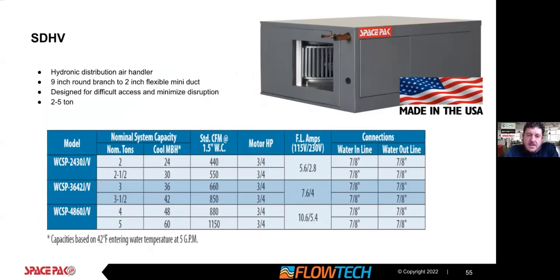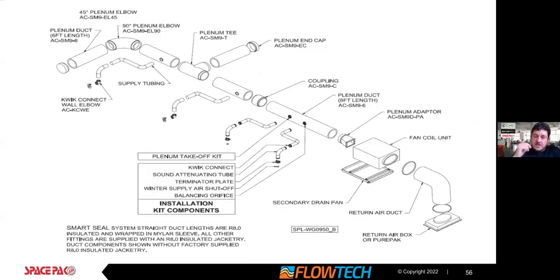They are easy to get into architectural places where, like modern architecture, it is very difficult to get ducting. The SpacePak air handler and high velocity system has smaller ducting requirements. This version is hydronic, so it's taking that chilled or heated water from the buffer tank and delivering heated or cooled energy to the house, between 2 and 5 tons. And you can see some data sets here. For me, it's easier to show with pictures.